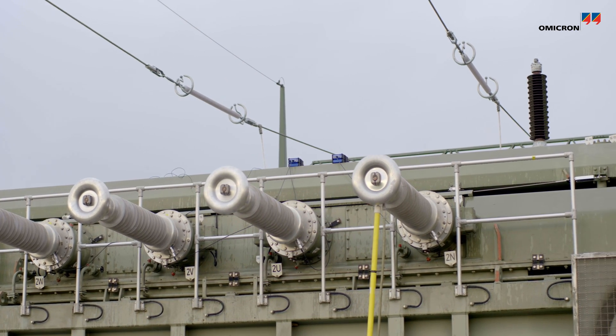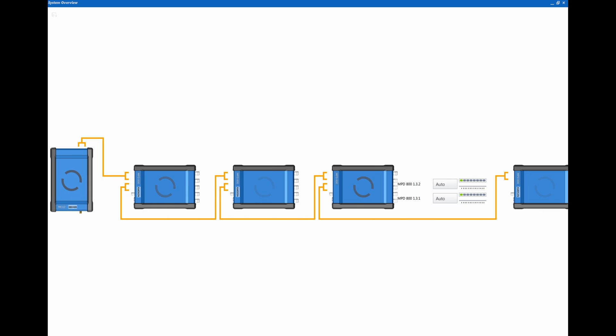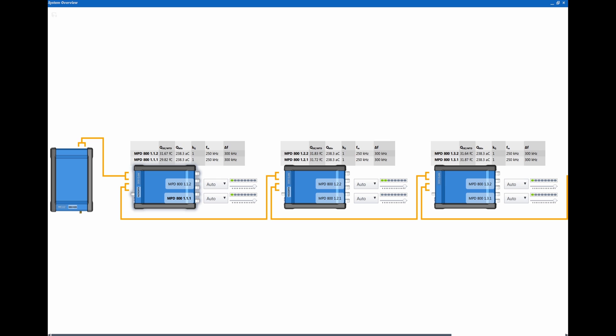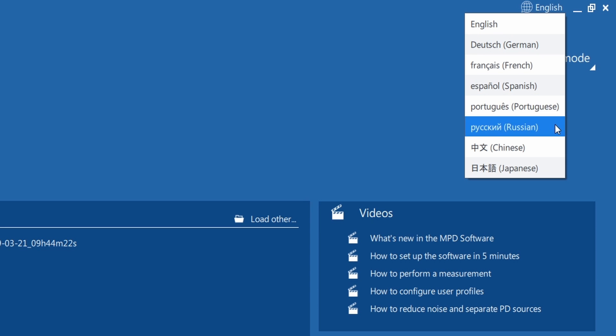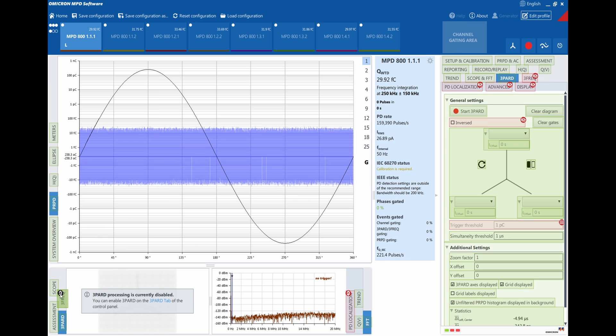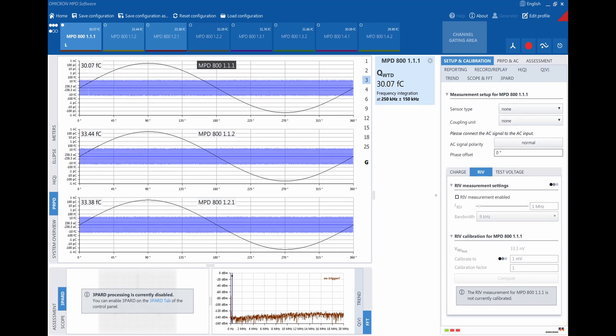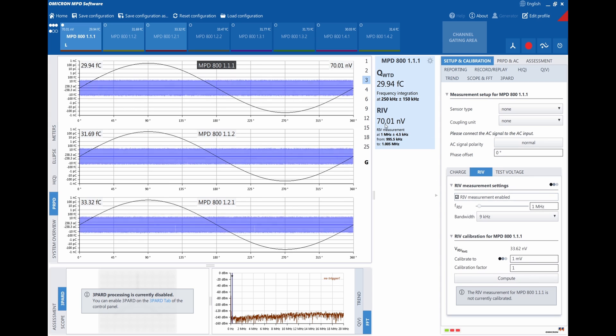Synchronous multi-channel measurements provide you with more information about the complete condition of the transformer's insulation system. The system's multi-language software allows you to select only the PD analysis tools you need and how data is displayed for specific tests. It performs simultaneous measurements of partial discharge and radio influence voltage for more efficient factory acceptance testing.